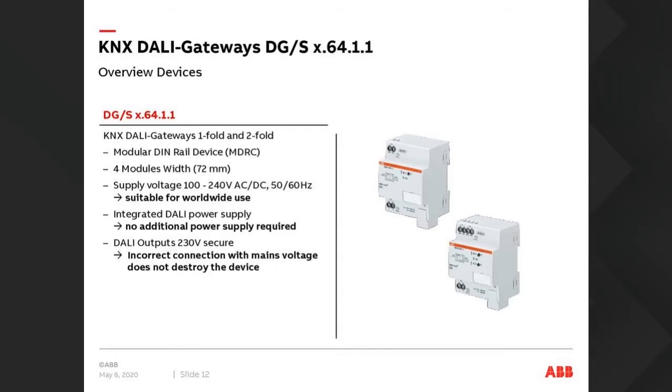You have a 230-volt connection on the bottom of it, so you don't need any external DALI power supply for the system. It's quite flexible in the voltage you can give it, 100 up to 240 volts, 50, 60 hertz. This device is sold globally, so you can see they've really put a lot of thought and effort into developing the devices.